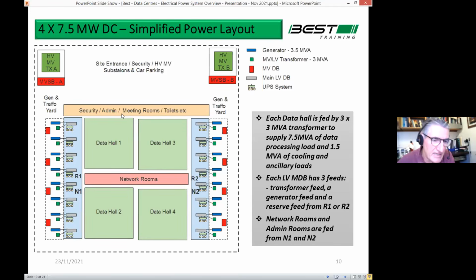So what we're going to look at first of all is the top left-hand corner and top right-hand corner, where you see HV/MV. That's where your transformers would go, out in a compound. These are massive transformers, probably 20 megawatt each, or 20 MVA to use the proper term. And they're in low cages. You keep them apart from one another in case the proverbial bomb hit one, it wouldn't damage the other, etc. And then somewhere else, which I haven't shown in the schematic, you have the ESB HV substation. This substation brings the supply in from the pylons, and it's not shown in the diagram because it could be anywhere, in any configuration.